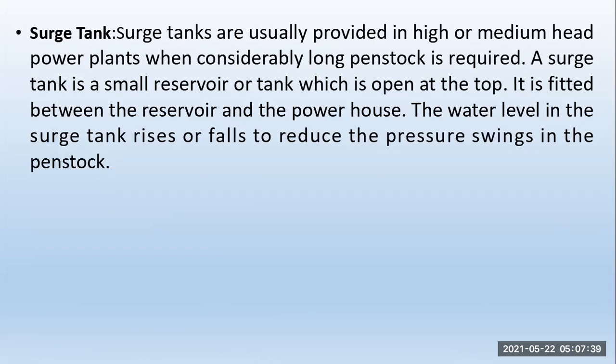Surge tank: surge tanks are usually provided in high or medium head power plants when a considerably long penstock is required. A surge tank is a small reservoir or tank which is open at the top. It is fitted between the reservoir and the powerhouse. The water level in the surge tank rises or falls to reduce the pressure swings in the penstock.